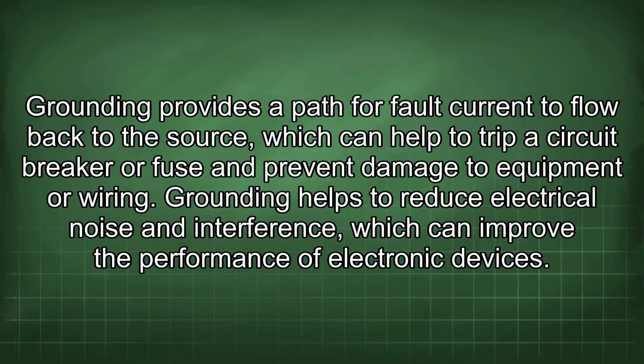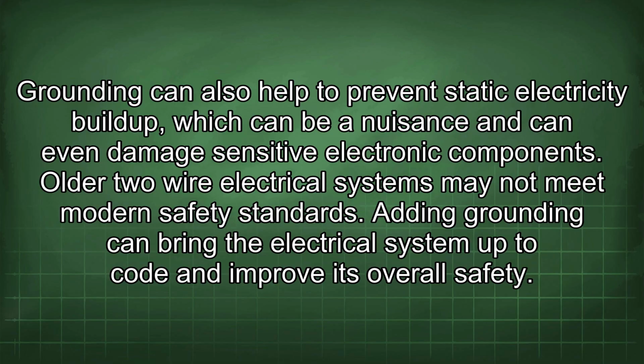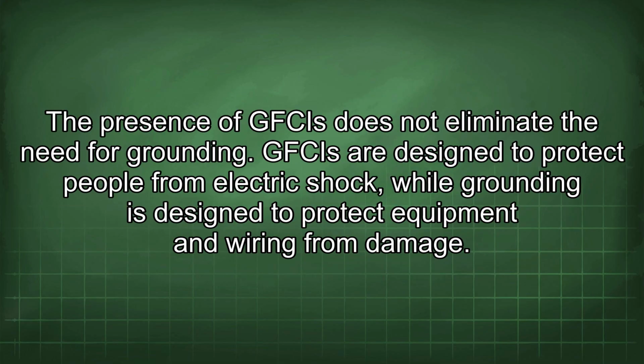Grounding helps to reduce electrical noise and interference, which can improve the performance of electronic devices. Grounding can also help to prevent static electricity buildup, which can be a nuisance and can even damage sensitive electronic components. Older 2-wire electrical systems may not meet modern safety standards. Adding grounding can bring the electrical system up to code and improve its overall safety. The presence of GFCIs does not eliminate the need for grounding. GFCIs are designed to protect people from electric shock, while grounding is designed to protect equipment and wiring from damage.